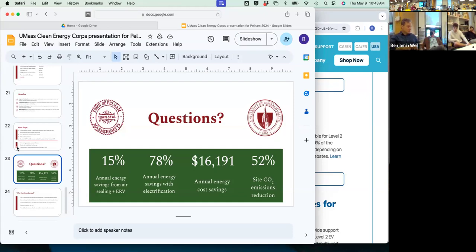In an ideal HVAC world, we would control all of our fresh air coming in by running it through the enthalpy energy recovery unit. But in the practical world, kids will be going in and out, doors will be open, folks will open windows. Are there studies about how that affects this kind of a system? So there are controls and then there are studies. So the controls, if the dew point sensor senses dew point rising, you may find that you're not getting sufficient sensible cooling because the dew point sensor has increased the water temperature to prevent condensation. The number of hours where that's going to be a problem, where people are so uncomfortable they complain, is small.